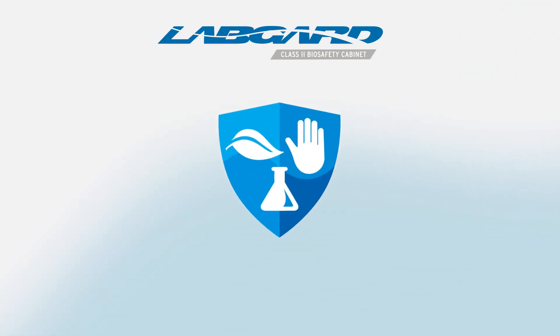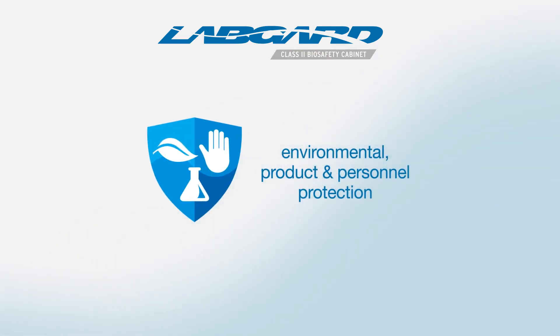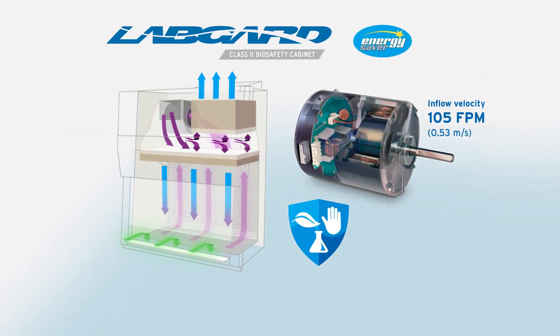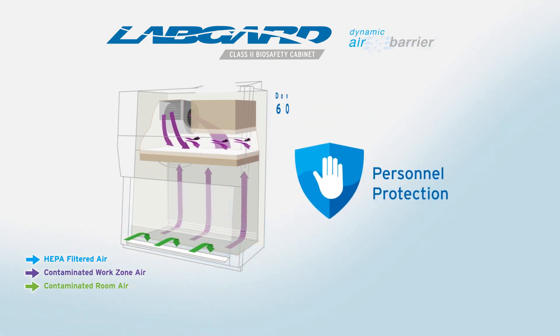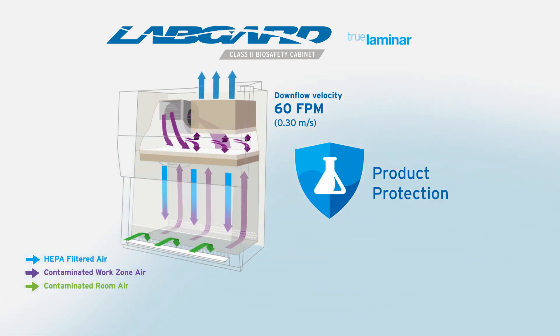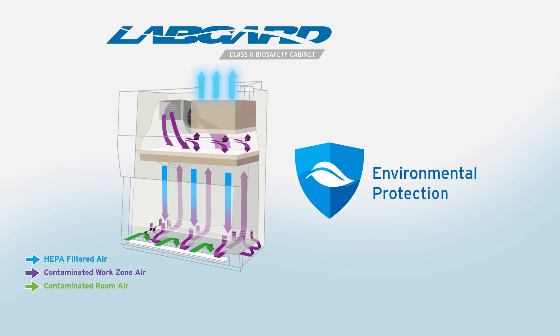Let's start with the fundamentals. As a Class 2 Type A2 biosafety cabinet, the LabGard NU543 provides a trifecta of protection for its owners. A single ultra-high efficiency motor achieves a strong inflow velocity for superior personnel protection, pushes downflow air through a flexible HEPX plenum and supply HEPA filter for improved laminarity and product protection against cross-contamination, and finally propels air through a large exhaust HEPA filter for exceptional environmental protection.